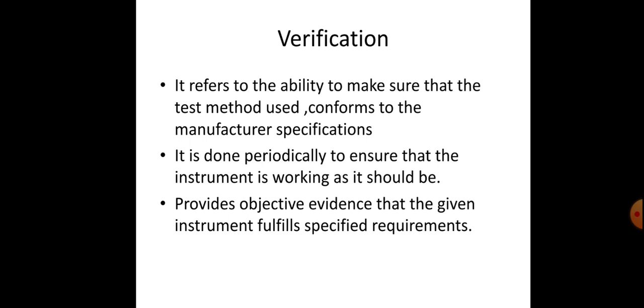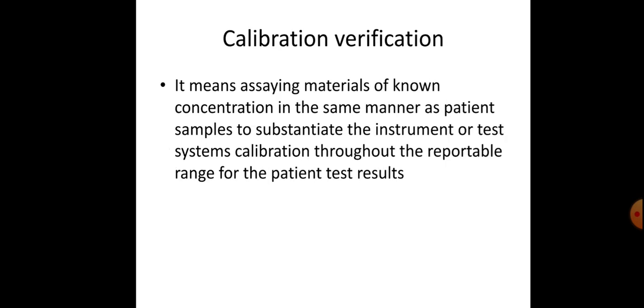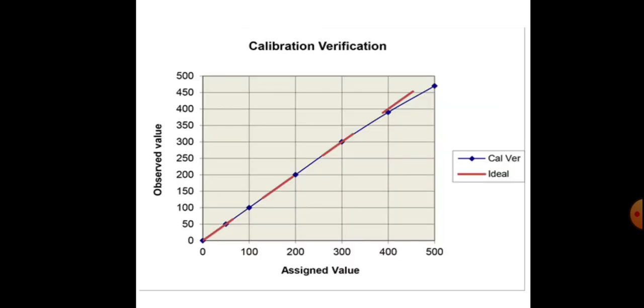Then verification. It refers to the ability to make sure that the test method used conforms to the manufacturer's specifications. It is done periodically to ensure that the instrument is working as it should. It provides objective evidence that the given instrument fulfills specified requirements. This is about verification. The combination of calibration and verification means assaying materials of known concentration in the same manner as patient samples to substantiate the instrument or test system calibration throughout the reportable range for patient test results.